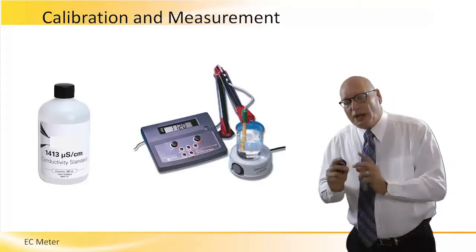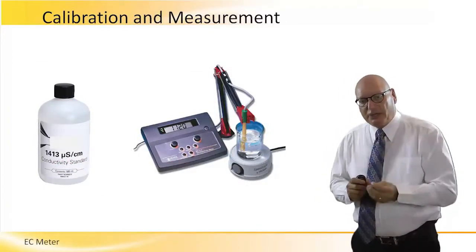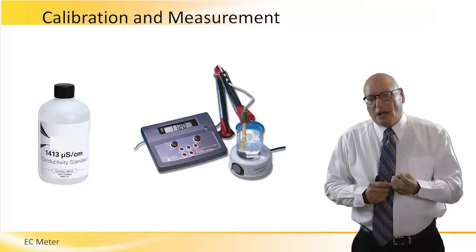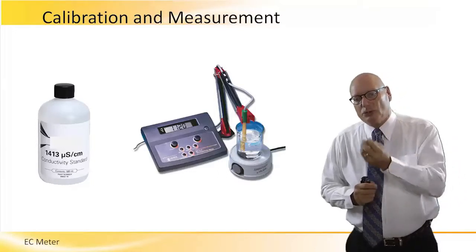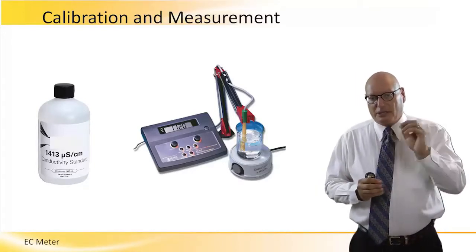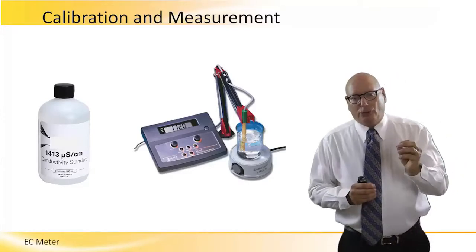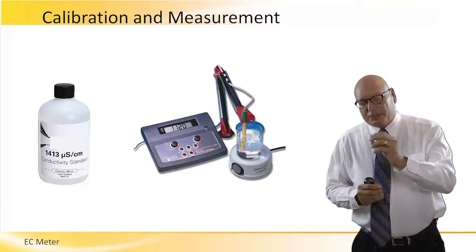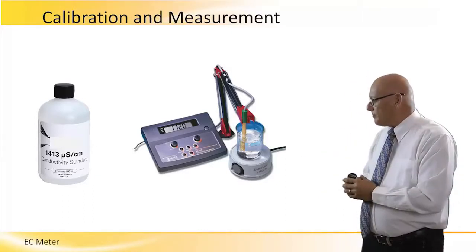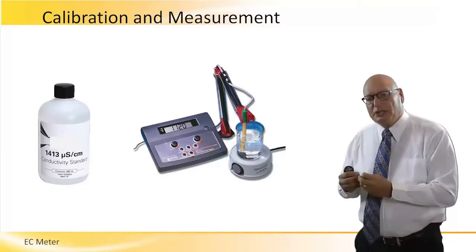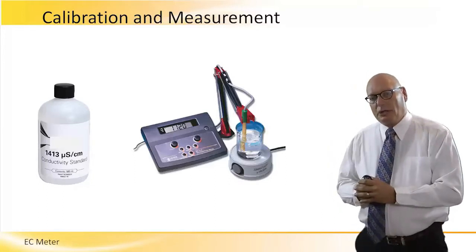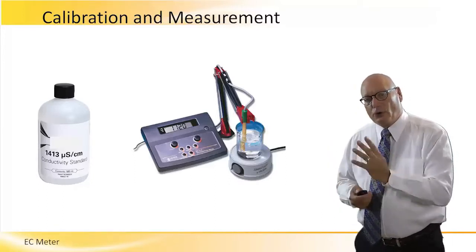In order to calibrate that particular system, we have specific bottles with materials which are actually used as a calibration solution. There are conductivity standards — for example, in this particular case, we have 1413 microsiemens per centimeter. And here on the right-hand side, there is a picture demonstrating how it's being tested. We can actually see the EC meter inside, dipped into the solution. Within it, there are four electrodes.